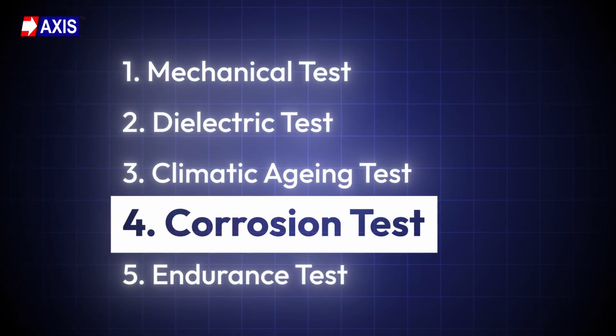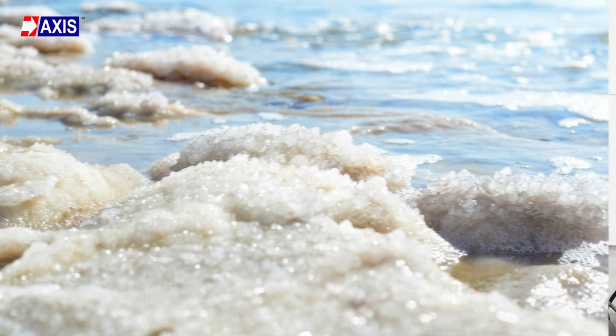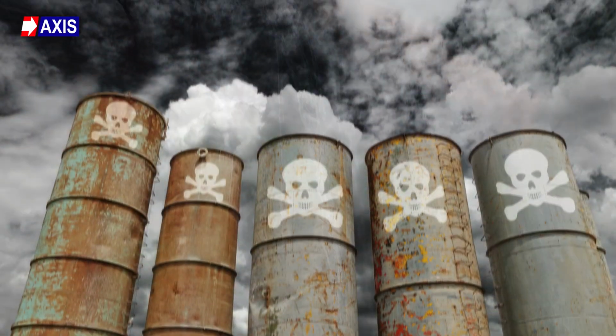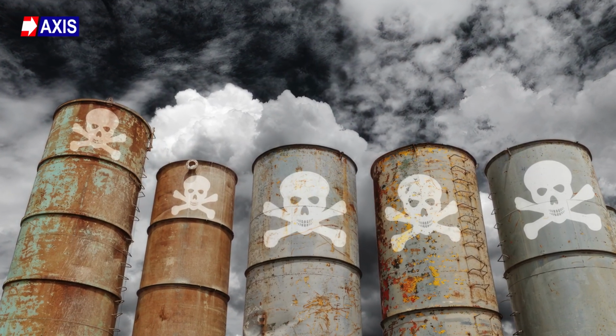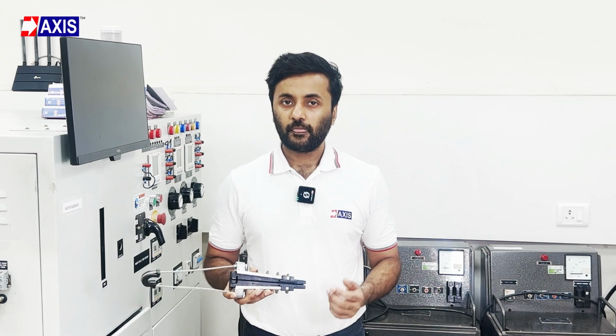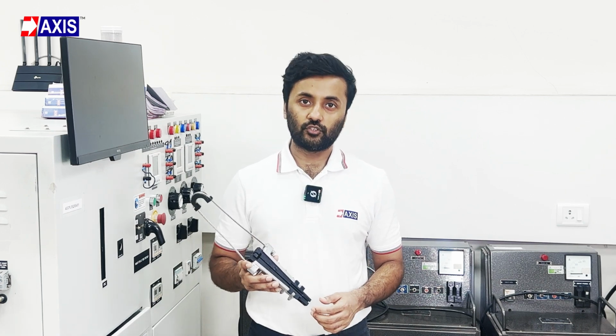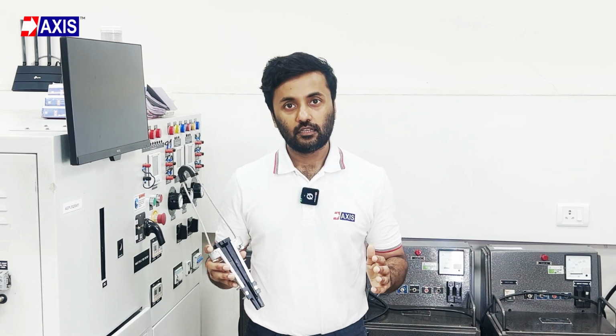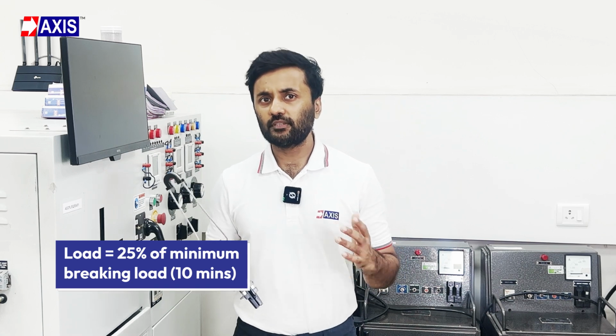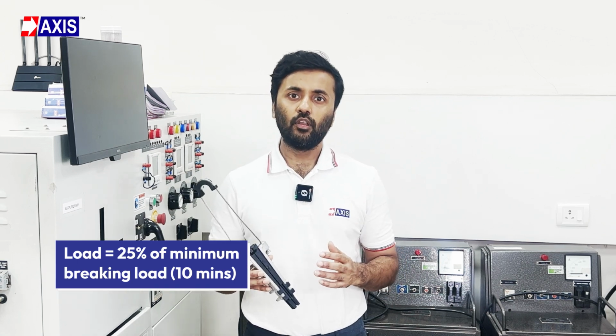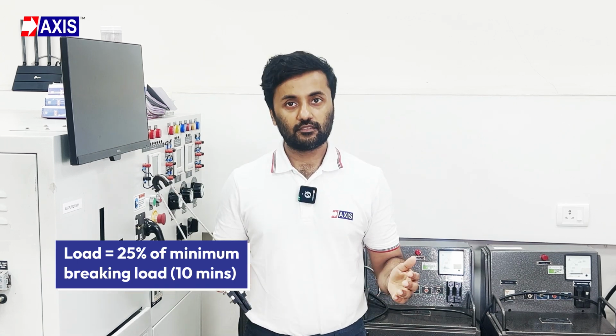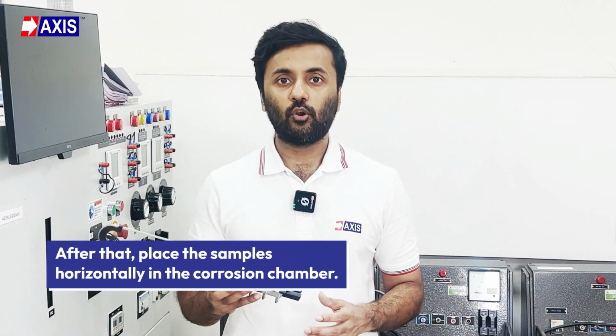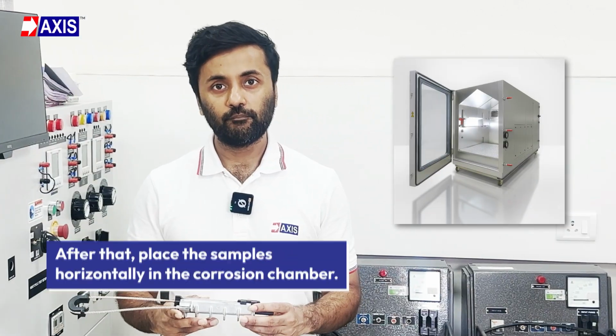Fourthly, the corrosion test. The goal of this test is to check whether the clamp can resist corrosion caused by salt, moisture, and/or pollutants in the outdoor environment. So how do you conduct this test? Install 2 clamps on a neutral messenger 500 mm apart. Apply a load equal to 25% of the minimum breaking load between the clamps for 10 minutes. After that, place the samples horizontally in the corrosion chamber.